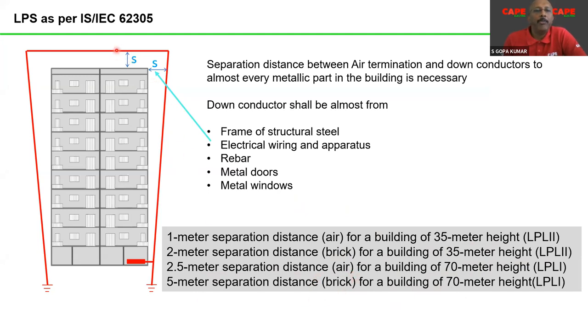The insulating material is nothing but, between the air terminal and the down conductor, you have to put some support. And if that support is brick, or if the distance which we are calculating from the air terminal to the metallic part is physically separated by brick, you need almost 5 meters for a 70 meter building with lightning protection level 1. This means the air termination system in the last case has to be 5 meters away from your RCC building. Just imagine, is this practically possible? Practically, keeping the air termination or down conductor away from the building is very difficult. You need to make a 5 meter, maybe FRP, support, and you have to make the mesh 5 meter above the building, on the side 5 meter away from the building, which is practically impossible.